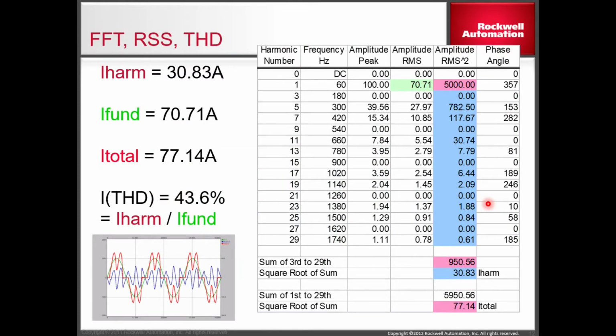Well, in this example here, our total current is 77 amps. 70 of it is fundamental working amps. 30 harmonic current amps are being produced. Now luckily it's not just a sum of the fundamental and the harmonic. It's a vector sum. So we can be thankful of that. But if you look here at this chart, the 5th and the 7th, you can see, are the biggest contributors to the harmonic distortion. The 11th has some, 13th, and so forth, but it gets smaller as we increase in the harmonic frequency.